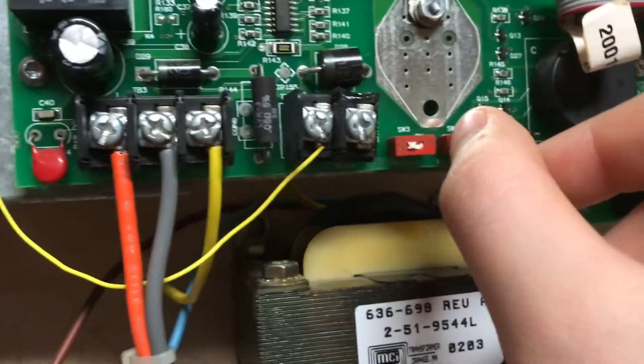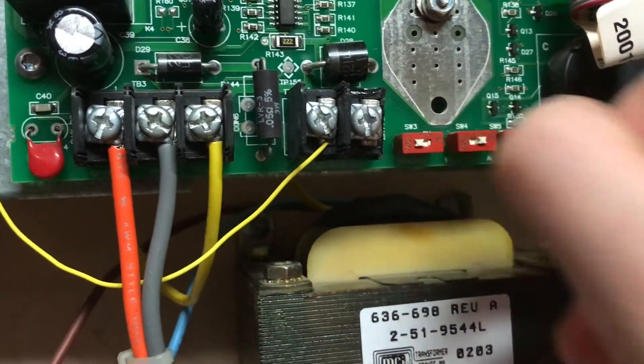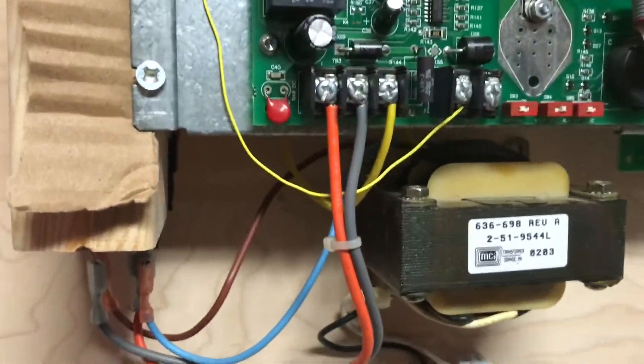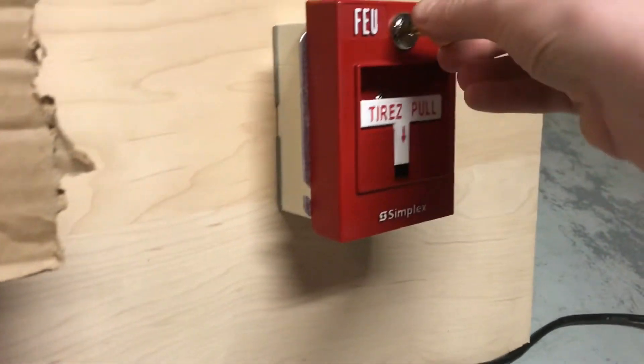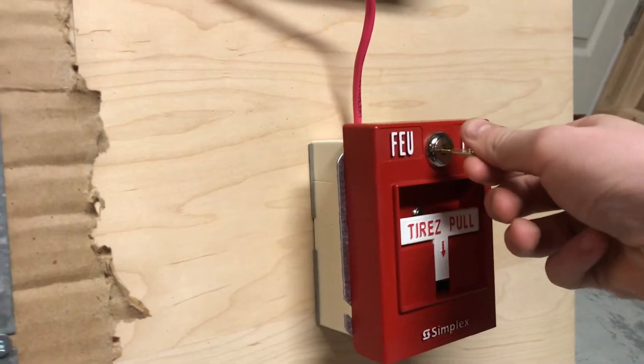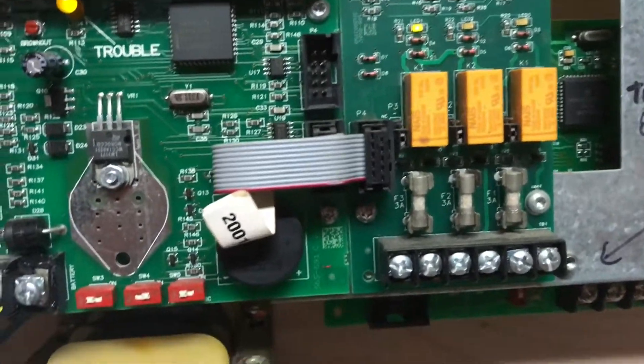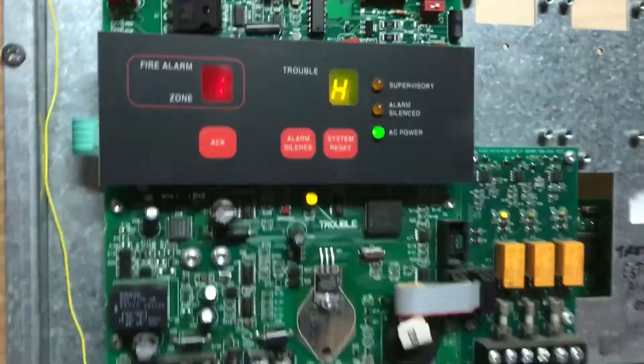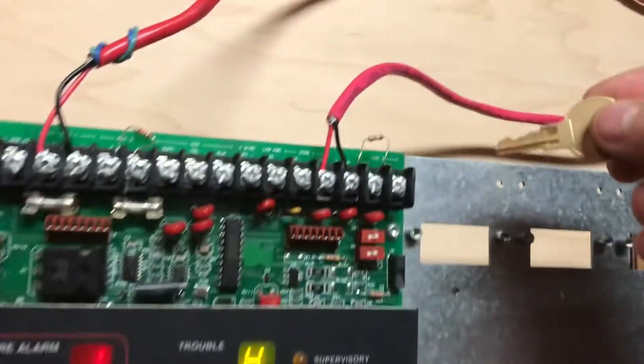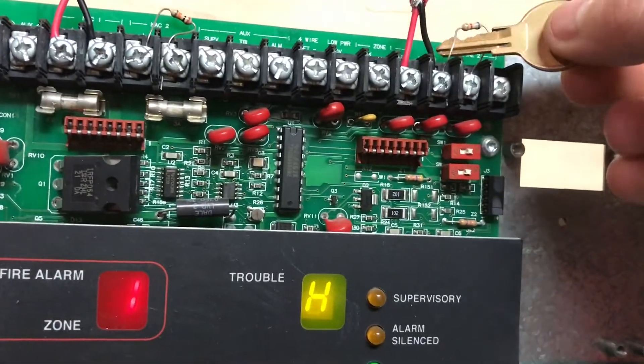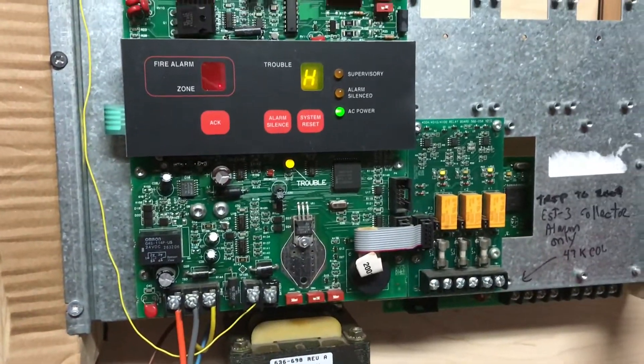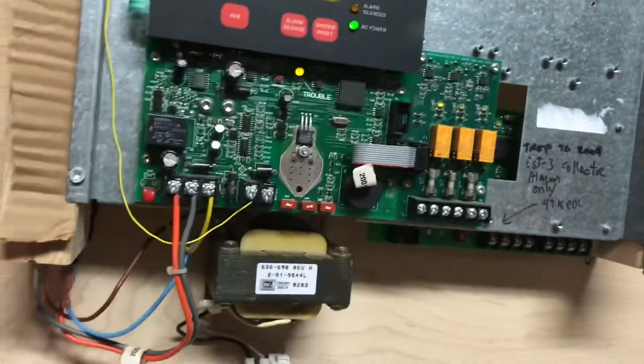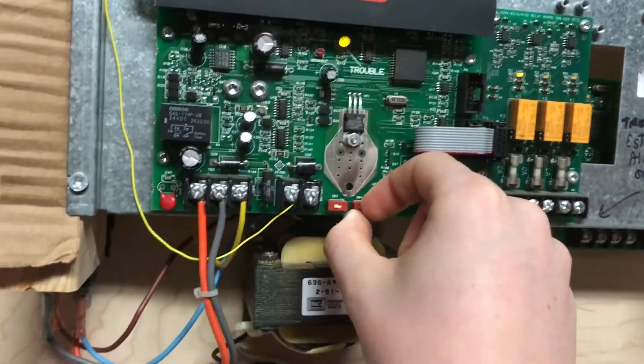Switch number four is for walk test. I don't really get why it would be H. Could have been a T or something like that. I will demonstrate at least zone one. So, you'll hear the relay click once. That's for zone one. The only thing I don't like is that it'll start beeping. I guess I can cross the terminal here and give a demonstration to the second zone. The strobe did flash, but that's it. So that's walk test for the 4004, so we can take that off.